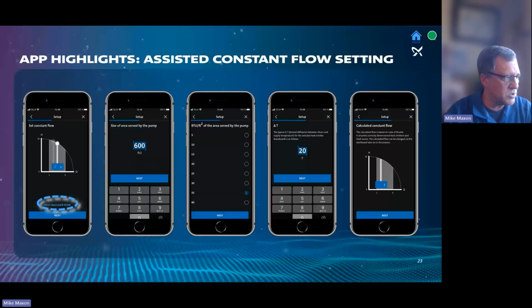We choose constant flow. The next screen is going to say, would you like to calculate this flow or just take the flow that you know? If you know that the flow should be 2 gallons a minute, set it for 2 gallons a minute and be done. Or we could do a calculation. Through this calculation, it's going to ask you what the size of the area of this zone is that we're heating, how many BTUs per square foot we need for this zone, and what delta T we want on the water flow. And then it's going to calculate that and give you a flow that you can set the pump at.